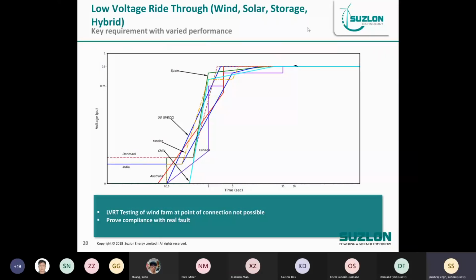At a high level, the most critical requirement we see in all grid codes is the low voltage ride through. Only the magnitude and duration vary. That's why in the curve, some grid codes require the voltage dip to go up to 0% residual voltage, some say 15%, some say 20%. The duration could be 150 milliseconds to 1 second.